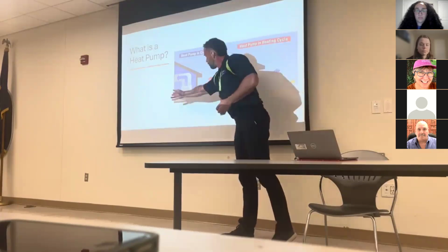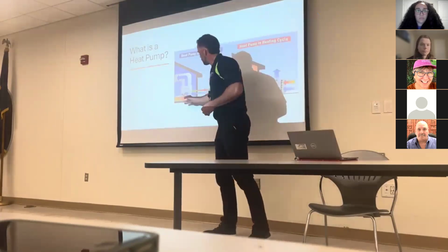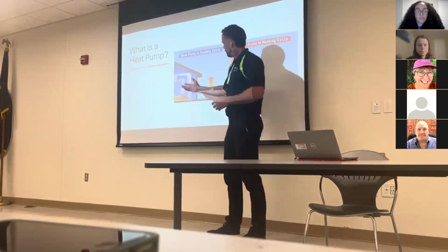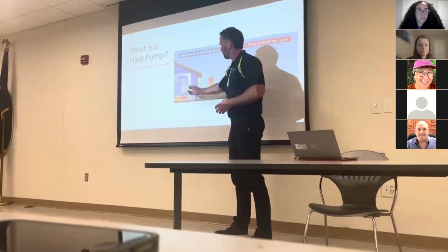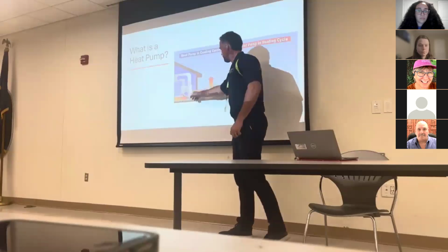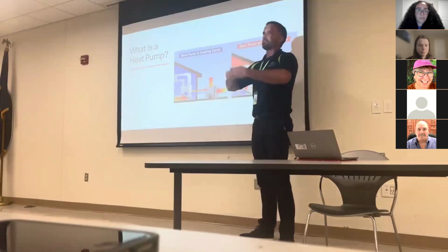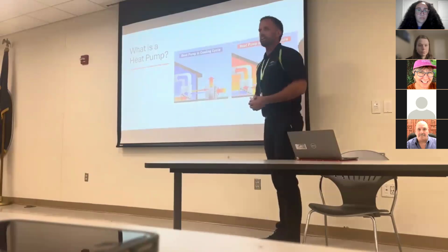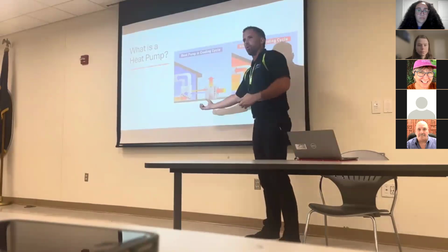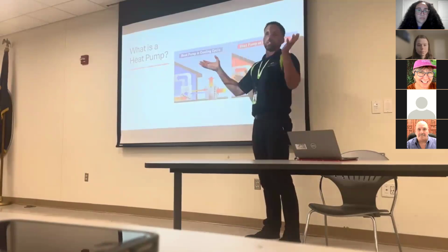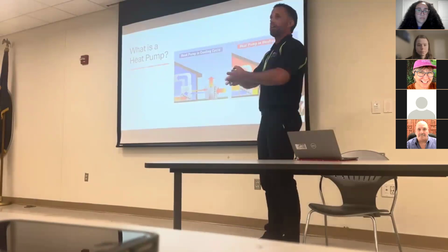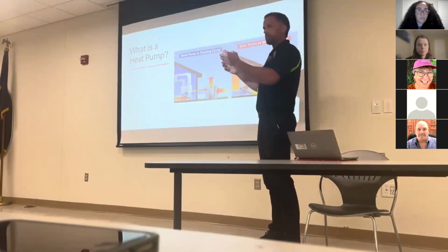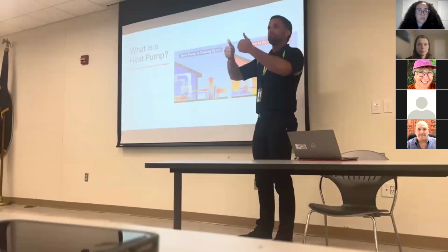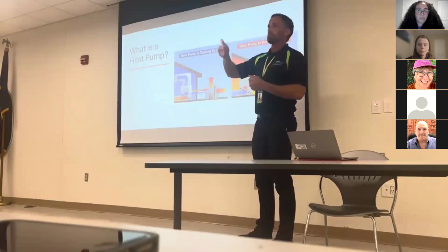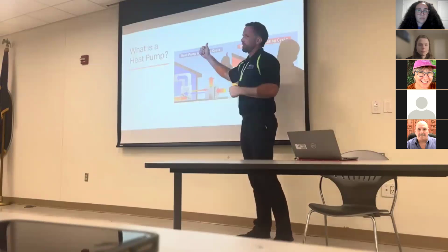You're taking the warm return air from your house, it blows over this coil here that's filled with cold refrigerant, and that cools the air off and it puts cold air back in your home. That refrigerant absorbs the heat from your return air, and it takes it back out to this outdoor unit where a fan blows over it and it blows all that heat outdoors. And there's compression in there. In order to get the refrigerant warm enough to reject heat into the air, if the air is 90 degrees outside, we have to get that refrigerant above 90 degrees in order to reject heat into 90-degree air. So that compressor squeezes down that refrigerant, which boosts up the pressure, and the pressure-temperature relationship, when one goes up, the other goes up. So we raise the pressure of that refrigerant.